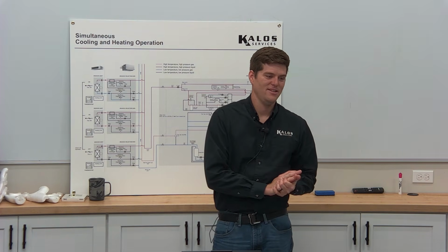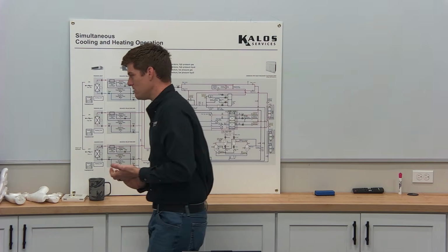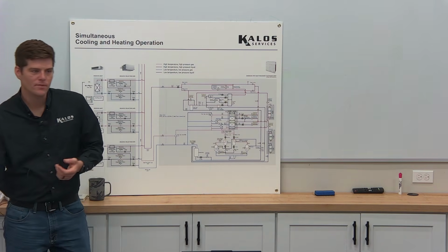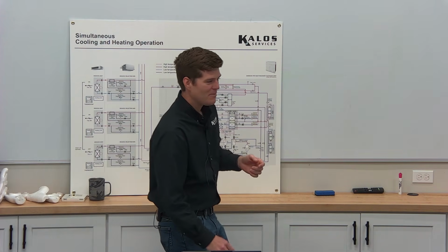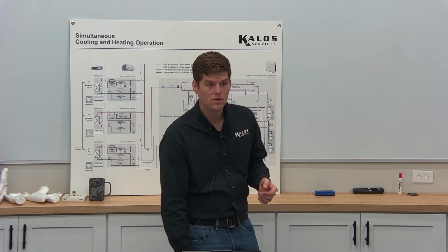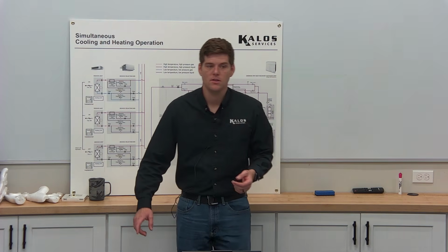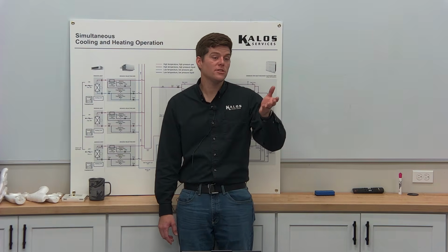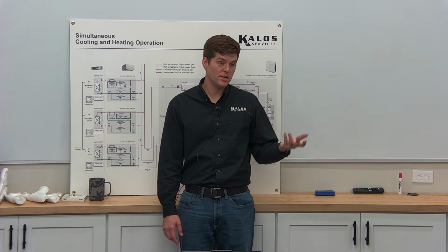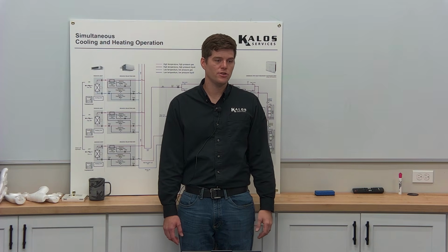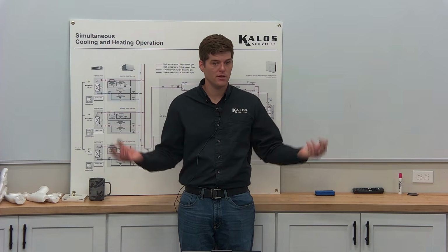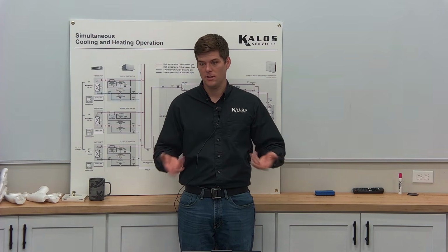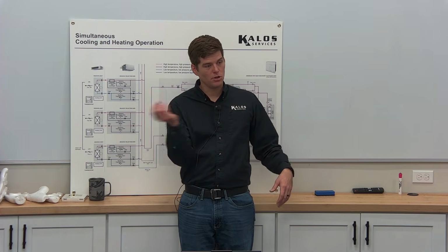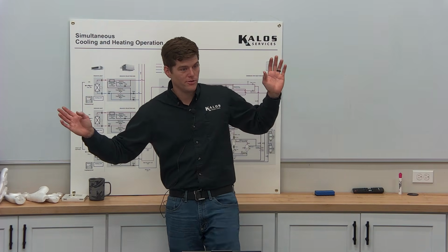Create a restriction. No, close. You're thinking. Reduce turbulence. Maybe. Definitely reduce turbulence because of the U shape instead of the T that kicks the pretty. Well, yeah, the T is awful. And at one point, Daikin used T's on their outdoor units, connecting them together, and it just creates a ton of turbulence. It creates a ton of restriction. It just literally is like throwing a water balloon at a wall. It just goes everywhere, right, in the refrigerant line.